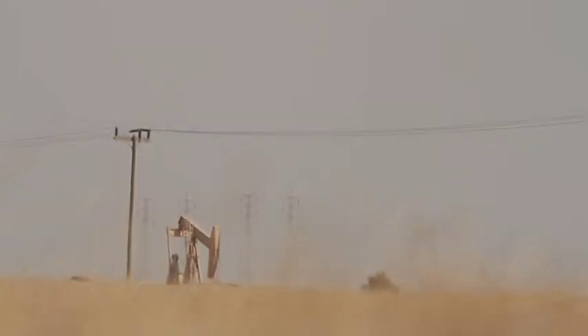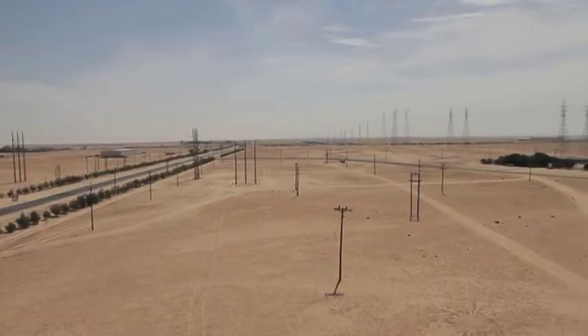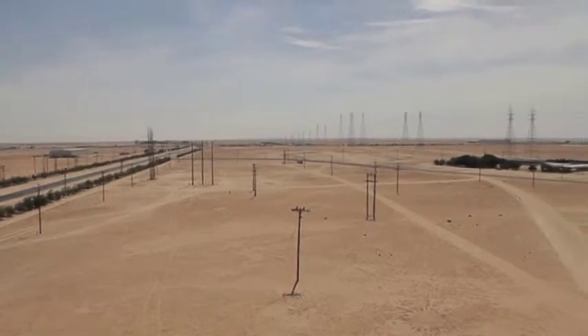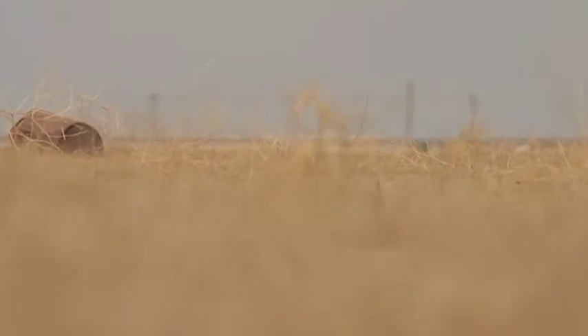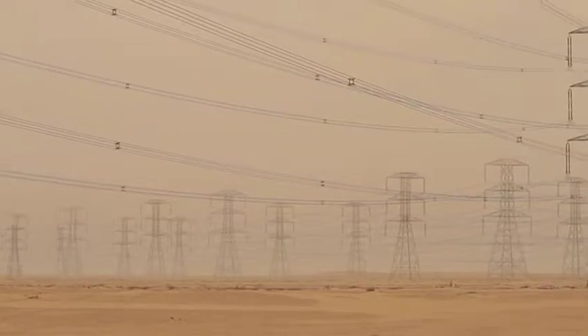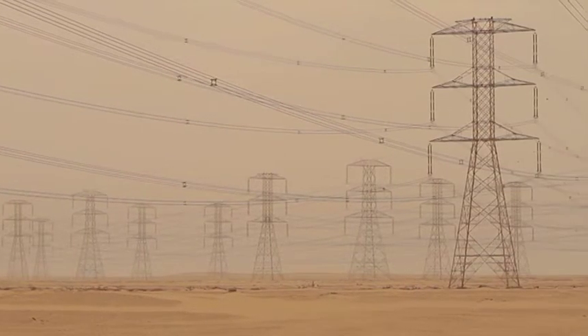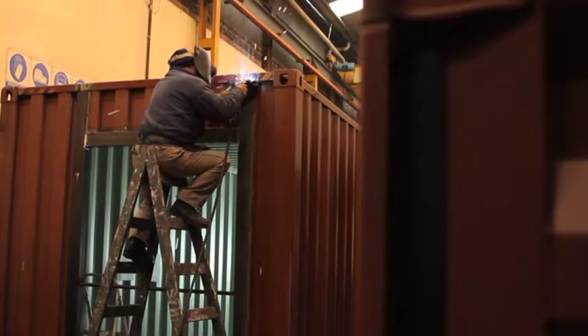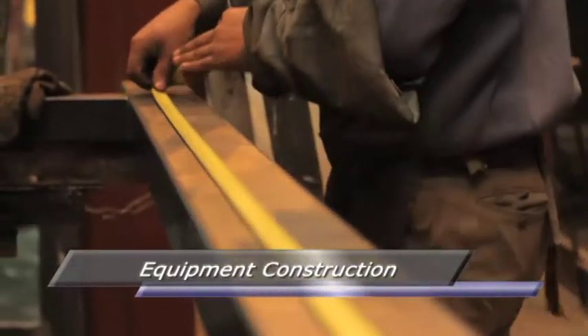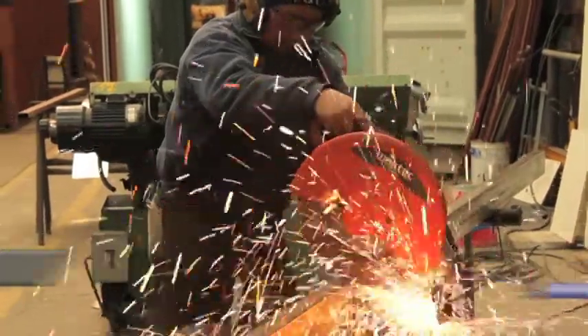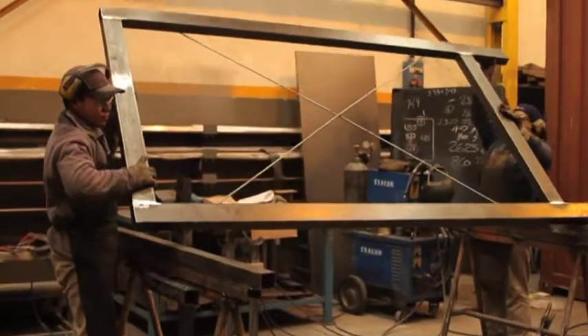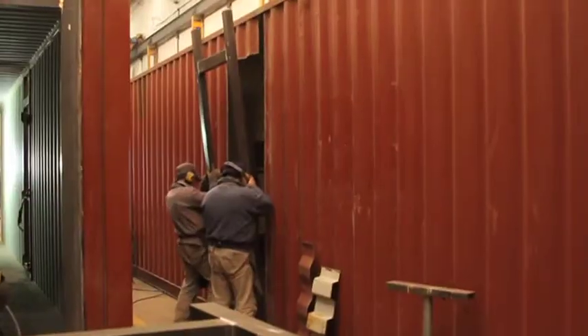The extreme desert climate conditions at the erection site, with maximum temperatures reaching 60 degrees Celsius in summer and frequent sandstorms, called for the use of enclosures with an IP65 degree of protection. This was implemented by the use of standard 20 feet containers for 11 kV harmonic filter banks and 40 feet high-cube containers for 33 kV harmonic filter banks.